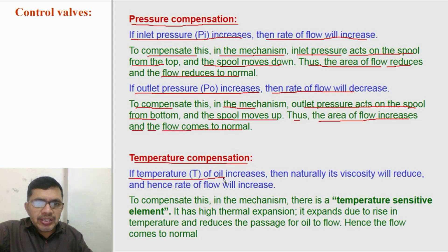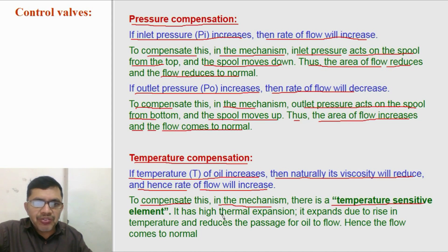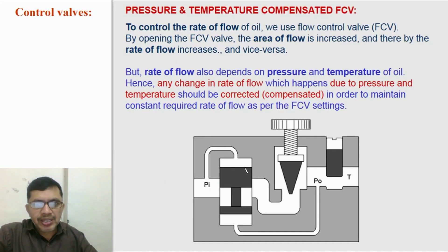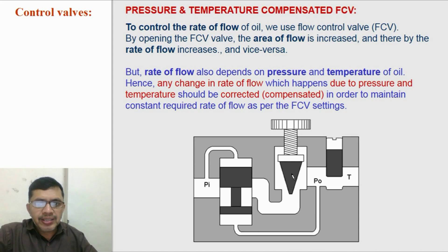Temperature compensation mechanism: if the temperature of oil is increased, then naturally its viscosity will reduce, due to which the rate of flow will increase. To compensate this, in the mechanism, there is a temperature sensitive element with higher thermal expansion. It expands due to rise in temperature and reduces the passage for oil to flow. Hence the flow comes to normal. This valve is a pressure and temperature compensated flow control valve — it has a mechanism for compensating the rate of flow due to change in pressure and a mechanism for compensating the rate of flow due to change in temperature.